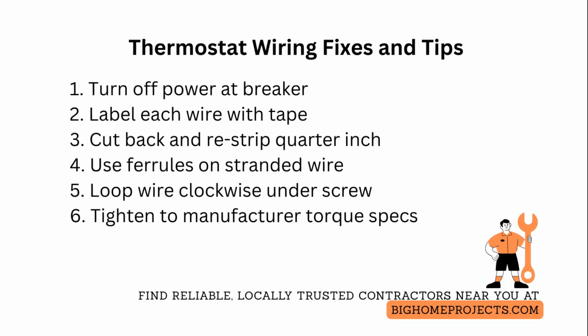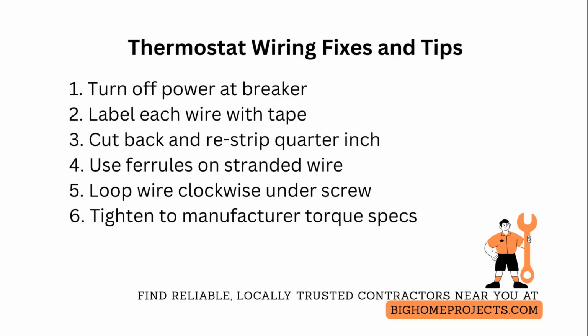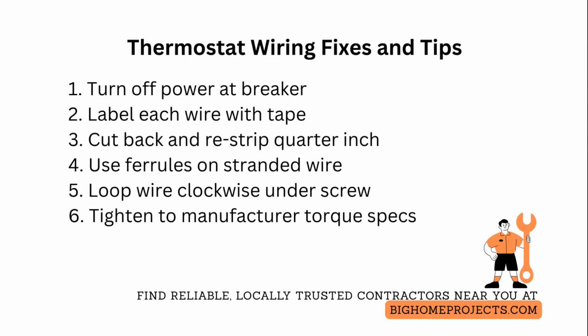When you seat the wire under screw terminals, place the bare conductor under the retaining prong or loop it clockwise around the screw so tightening draws the wire in, not out. For push-in terminals, verify the wire diameter matches the terminal spec and that insulation is fully retracted from the contact.